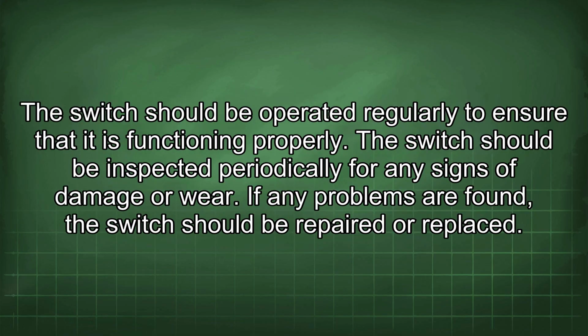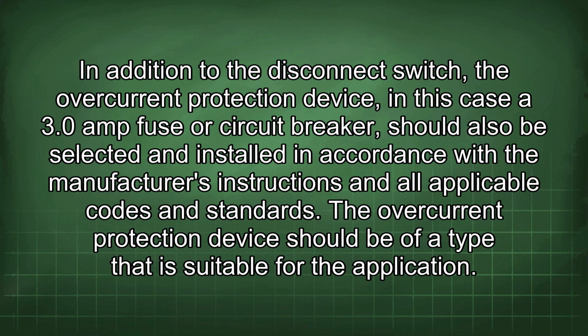The switch should be operated regularly to ensure that it is functioning properly. The switch should be inspected periodically for any signs of damage or wear. If any problems are found, the switch should be repaired or replaced. In addition to the disconnect switch, the overcurrent protection device, in this case a 3.0 amp fuse or circuit breaker, should also be selected and installed in accordance with the manufacturer's instructions and all applicable codes and standards.